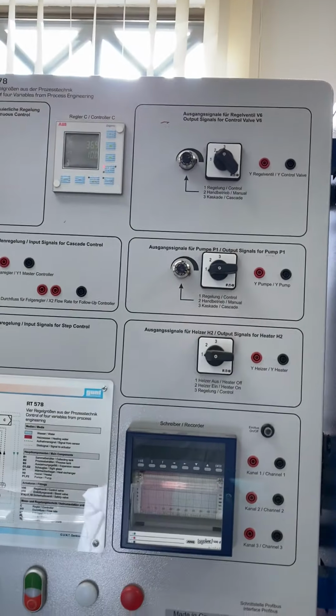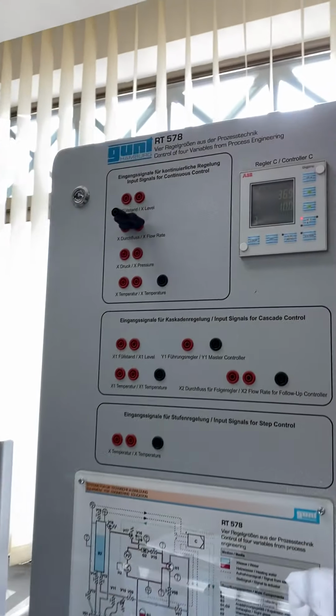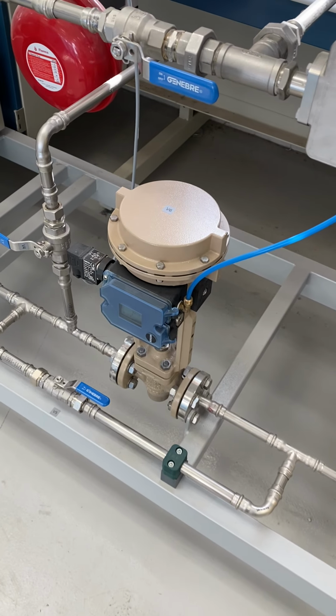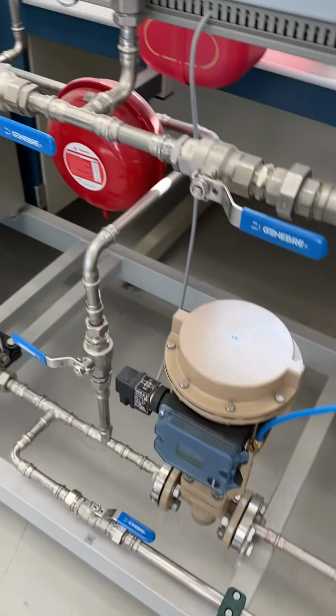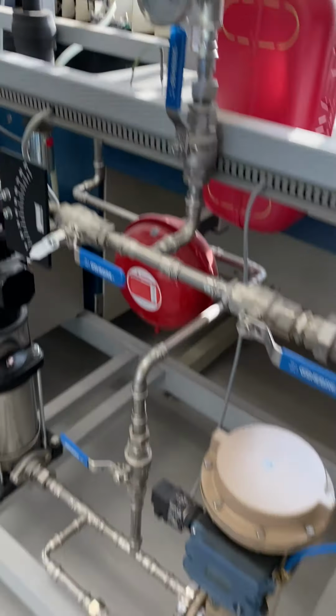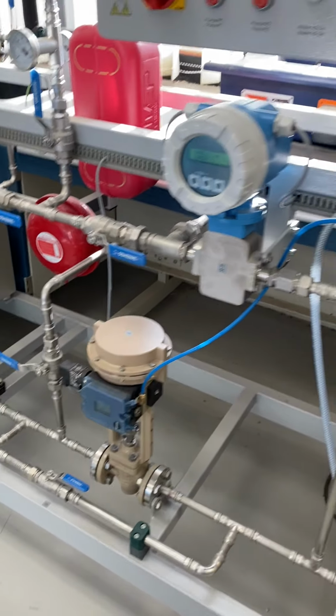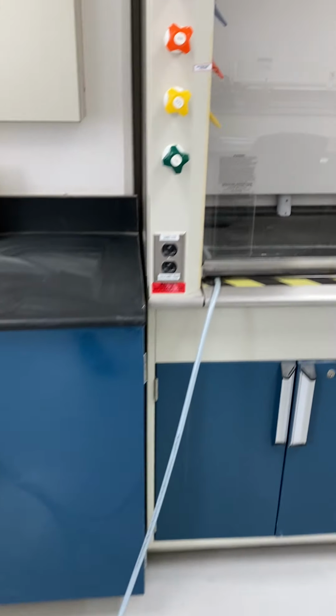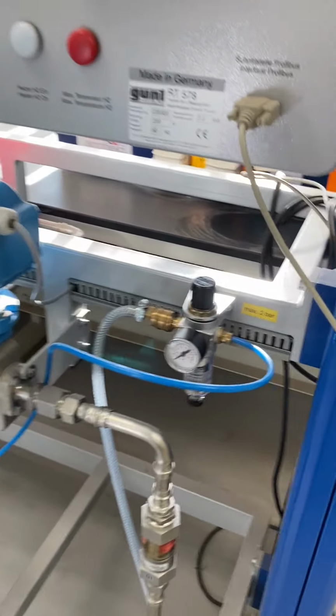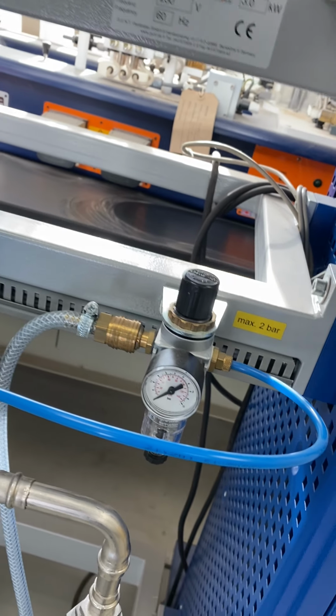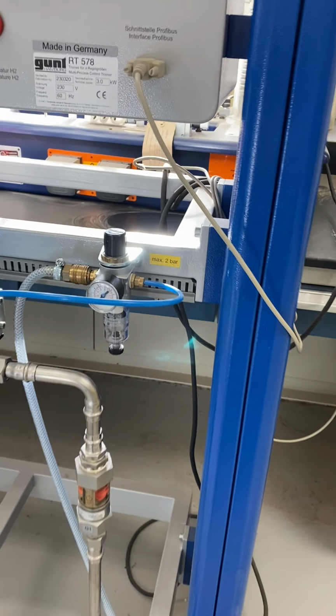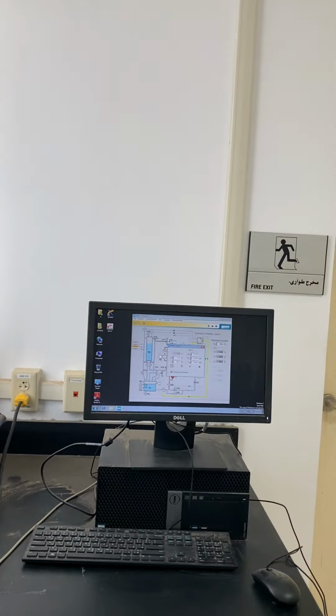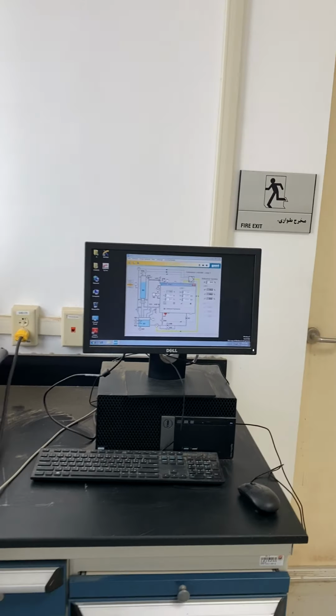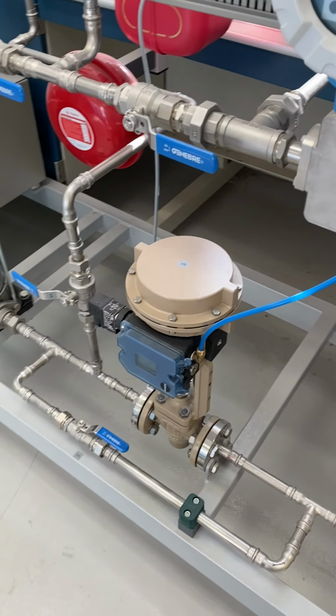The other actuator or final control element that we can utilize to control our process variables in here is the automatic control valve. So that is different from the manual valves that we have in here as well. This valve opens and closes automatically based on a pneumatic signal that is provided from here as well. So we have a compressed air supply from here, and it flows through the hose. We have a pressure regulator here, and you'll see, inshallah, that for safety purposes we have to maintain the pressure here at a value not exceeding 2 bars. And based on the values that will be set here on the controller, whether it is the remote or the local controller, the valve automatically opens and closes.